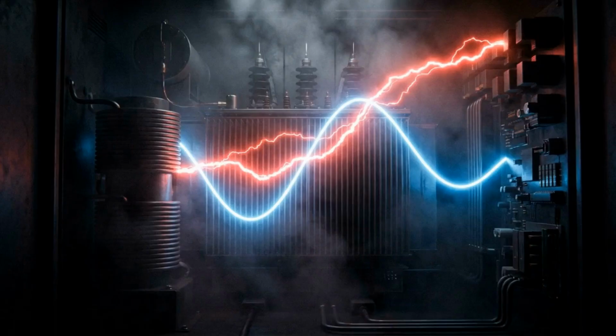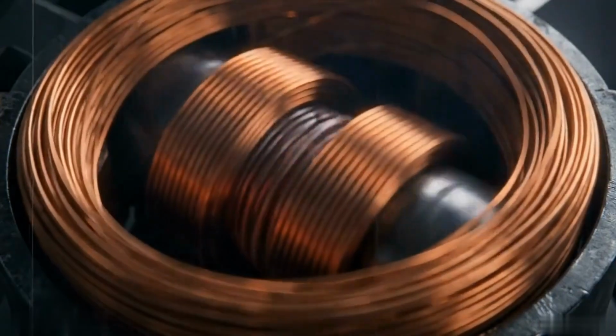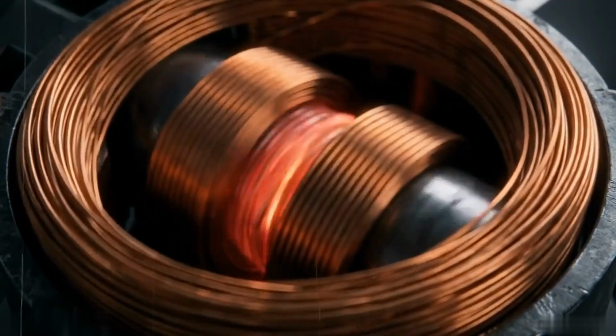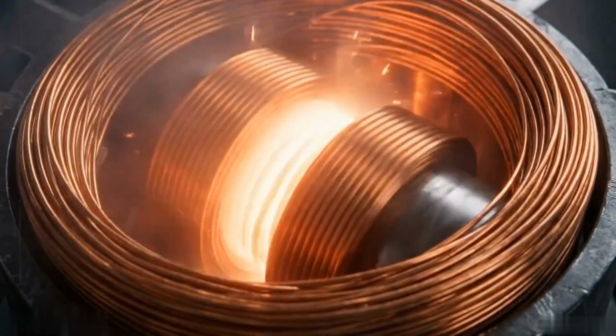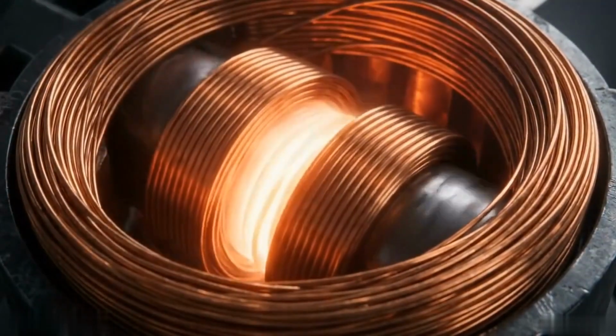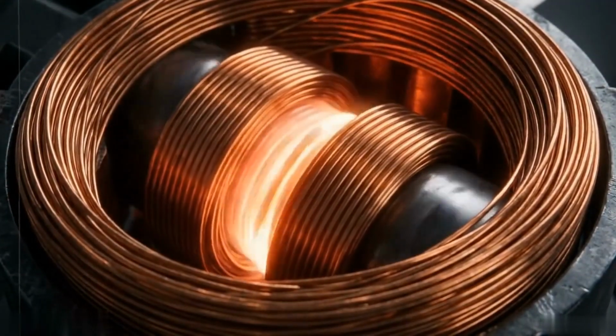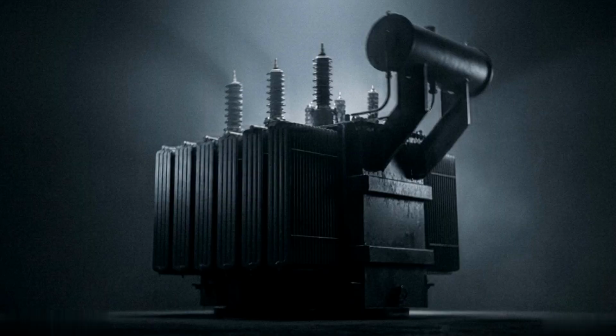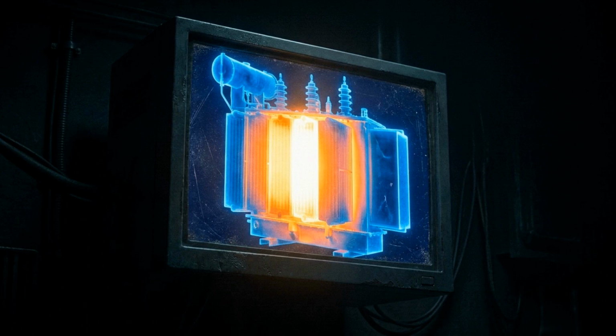Once inside, the direct current from the storm clashes with the alternating current of the grid, triggering a mechanical flaw known as half-cycle saturation. The magnetic core of the transformer becomes completely overloaded. The intense magnetic stress forces these multi-ton machines to physically vibrate. They emit a loud, low-frequency moan, and the copper coils inside rapidly begin to heat up far beyond their design limits.